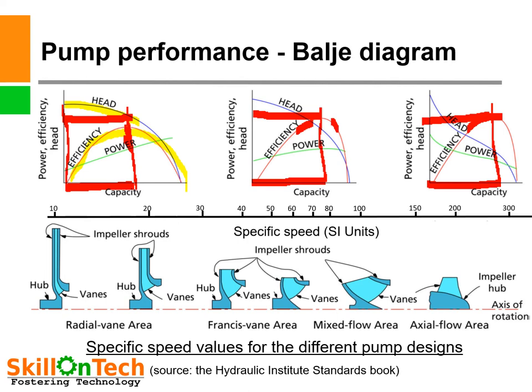Another difference visible in the diagrams is the shut-off head and power curve. Radial flow pumps take less power at shut-off compared to mixed flow and axial flow pumps. You can also see the specific speed classification of all three pump types: pumps with specific speed less than 30 come under radial flow pumps, and so on as shown in the diagram.